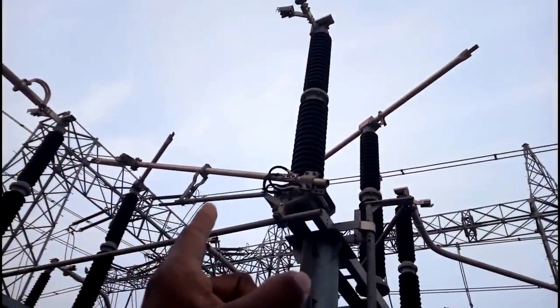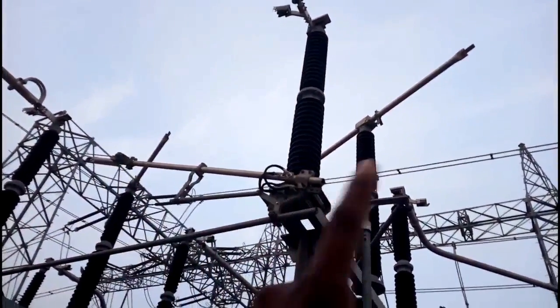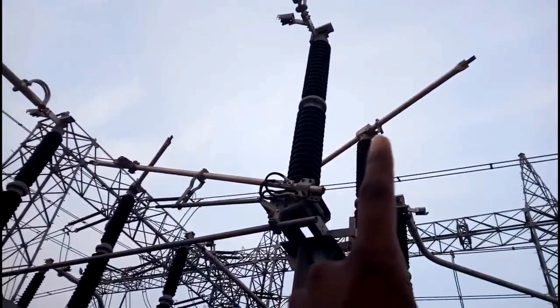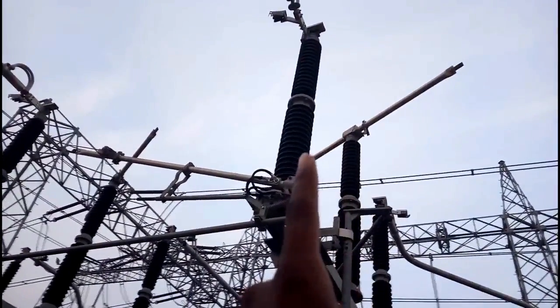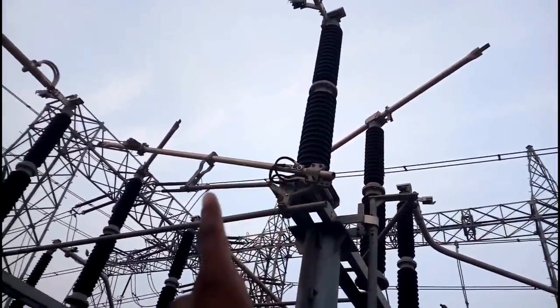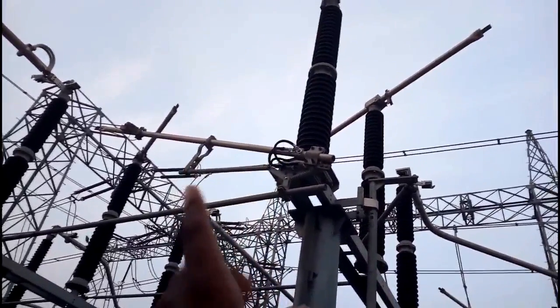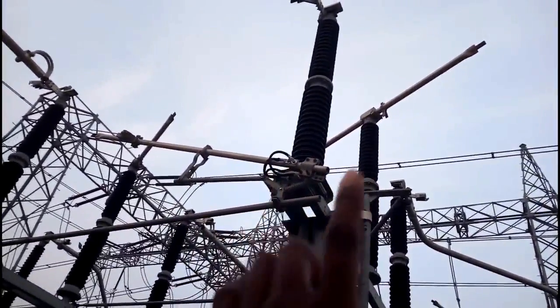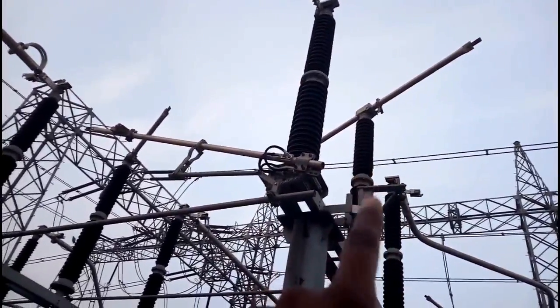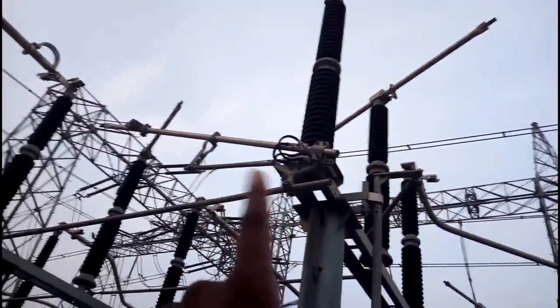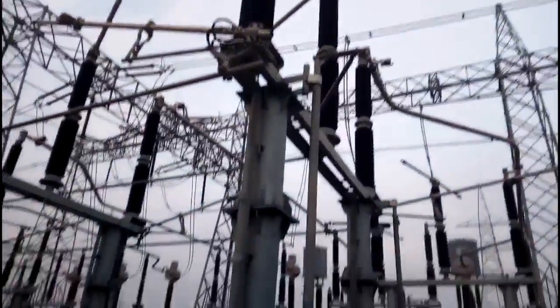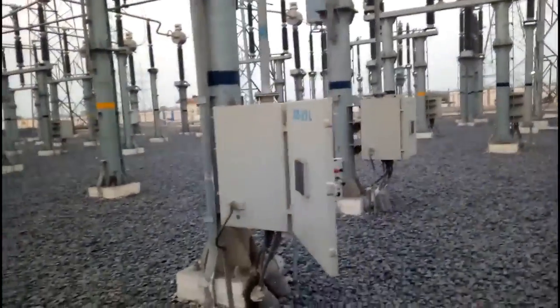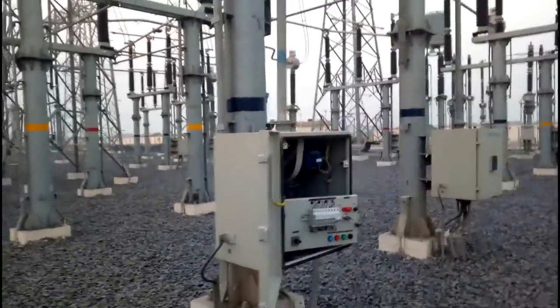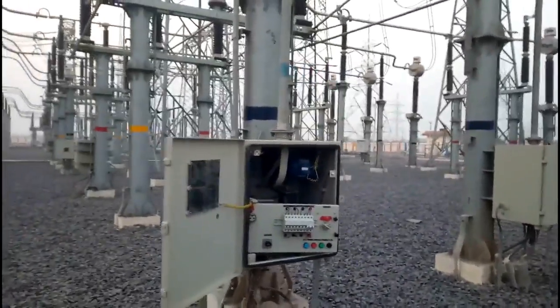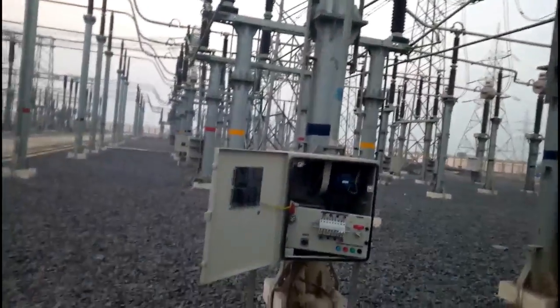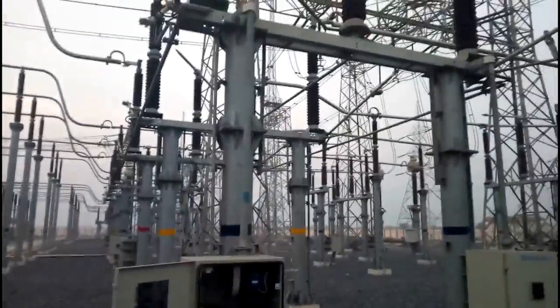This operation will be done electrically only when your isolator is in open condition. When your isolator is in closed condition, you cannot close this. It should be in open condition. These are the interlocks between the isolator main disconnecting switch and this earthing switch. Okay, so now I will show you the operation. However, there are electrical interlocks and mechanical interlocks. Both interlocks are provided and designed for the operation of the isolator.